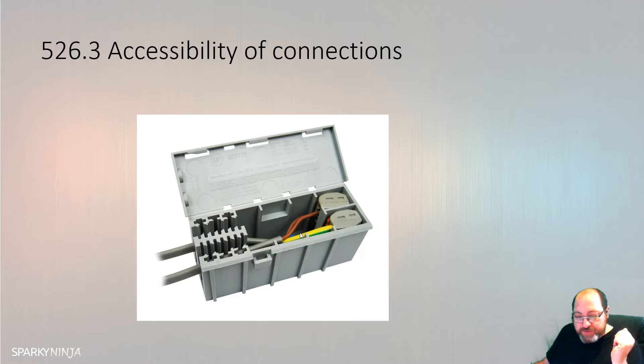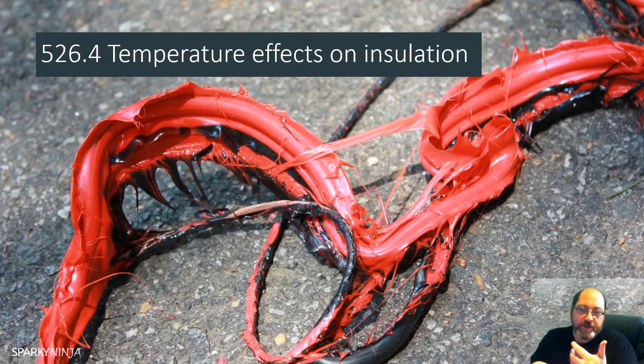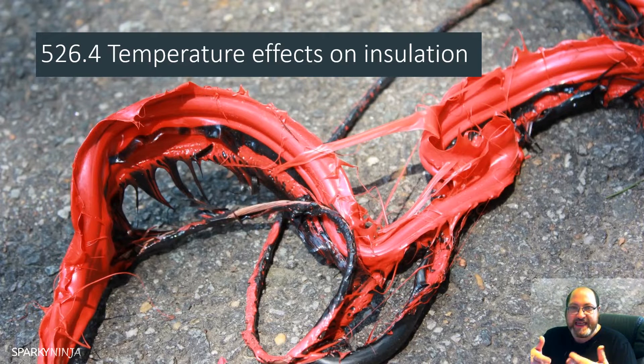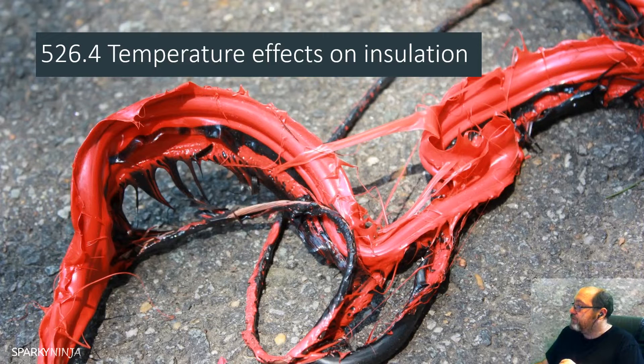We then have 526.4: where necessary, precautions will be taken so the temperature attained by a connection in normal service will not impair the effectiveness of the insulation of the conductors connected to it, or any insulating material used to support the connection. You've got to understand if there is thermal cycling or rapid changing loading, there will be an overall heating effect that may be inherent on the cabling or adjacent cabling. You have to consider the working temperatures of all connections.